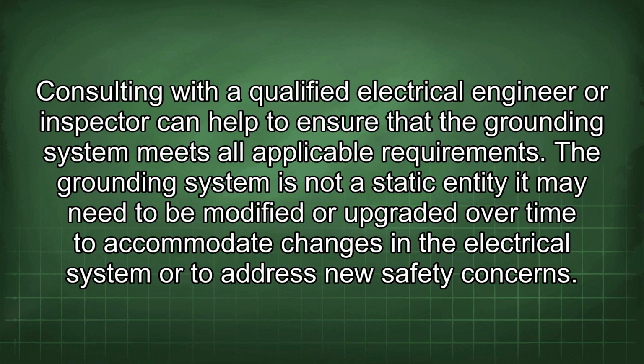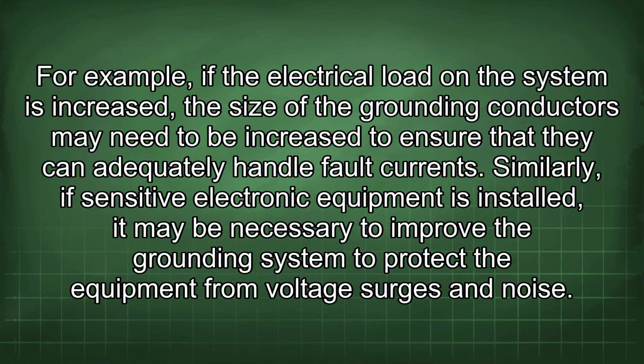The grounding system is not a static entity. It may need to be modified or upgraded over time to accommodate changes in the electrical system or to address new safety concerns. For example, if the electrical load in the system is increased, the size of the grounding conductors may need to be increased to ensure that they can adequately handle fault currents. Similarly, if sensitive electronic equipment is installed, it may be necessary to improve the grounding system to protect the equipment from voltage surges and noise.